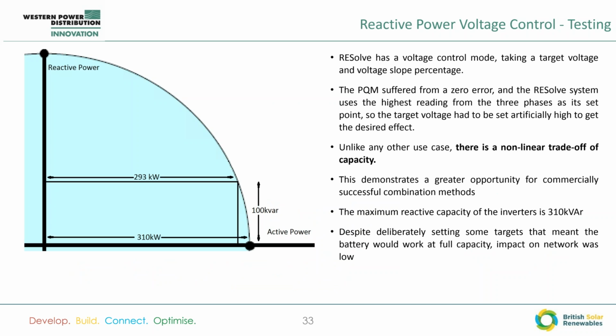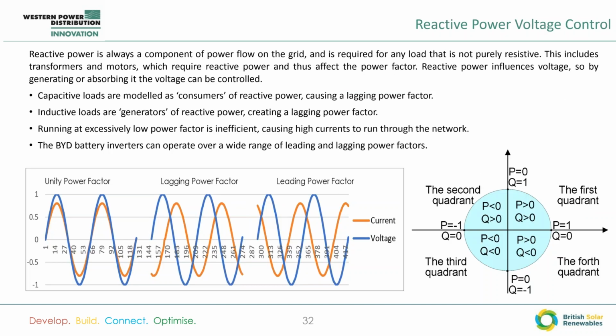We can see here a section, actually I'll just briefly go back there. That graph on the bottom right shows the active power P versus the reactive power Q of the inverters. So they had a perfectly circular PQ curve. They're able to operate anywhere inside that circle, which means there doesn't have to be any active power flow at all from the battery to be able to import or export reactive power.